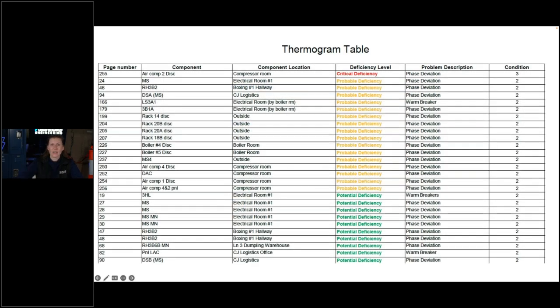So there's the example of a thermography table. It lists everything that was scanned, the deficiency level, and the problem description, such as whether there's a deviation between phases or the entire thing is overheating. Off to the right you'll notice a condition number, and it aligns with what we discussed earlier regarding equipment condition for maintenance interval modifications.